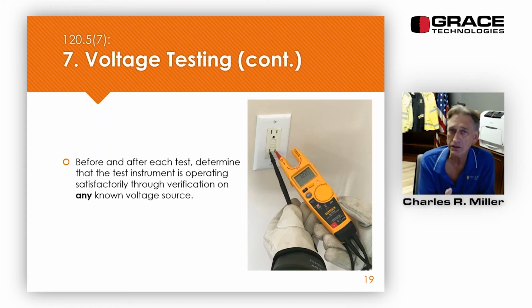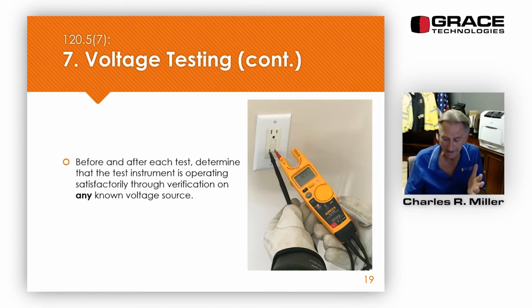But I caution against having most meters, a multimeter, check a battery and then check an alternating current load. Because most multimeters, you have to change it from DC to AC, back to DC, and if someone forgets part of that, then they may not get a true reading for testing for the absence of voltage. Now, the meter I have in this picture is a Fluke meter. Fluke absolutely makes great products. T61000. Now, this meter happens to have one dial setting for both DC and AC. So it wouldn't be as much of a problem checking a DC battery source.